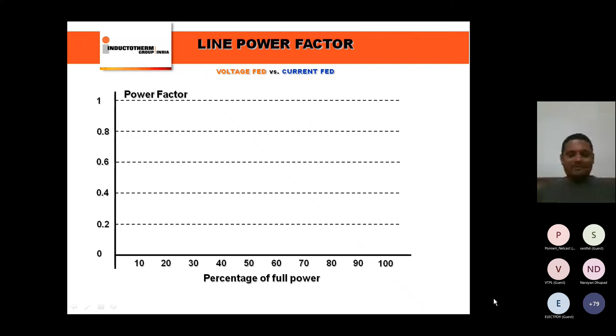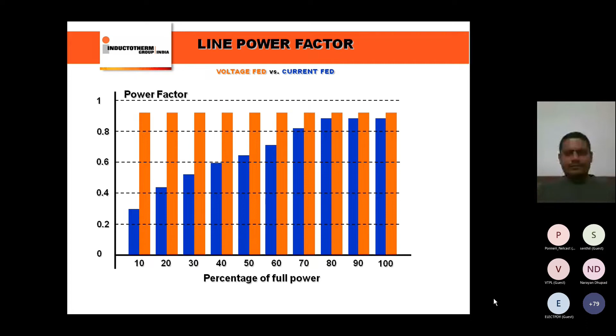Second is the line power factor. The power factor is very key nowadays everywhere. In some companies, the power factor should be proportional to the kilowatt rating, whereas Inductotherm gives a constant power factor irrespective of any power levels. So that implies lower the kilowatt, lower the kVA.